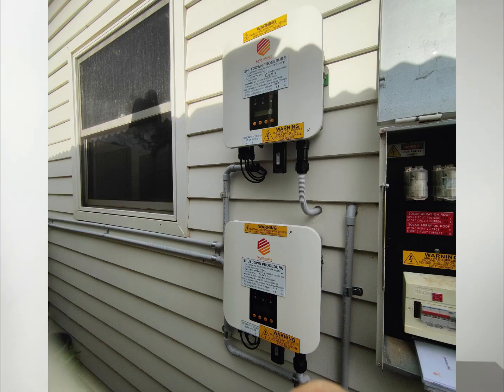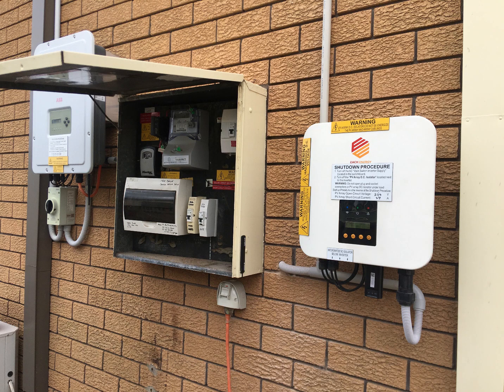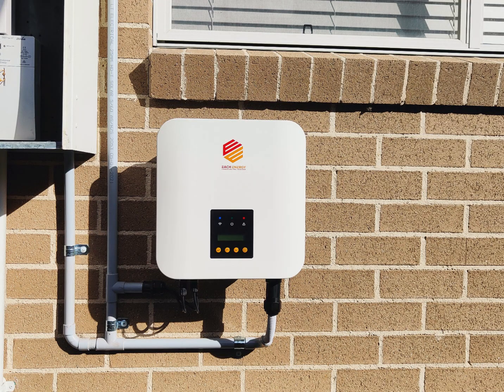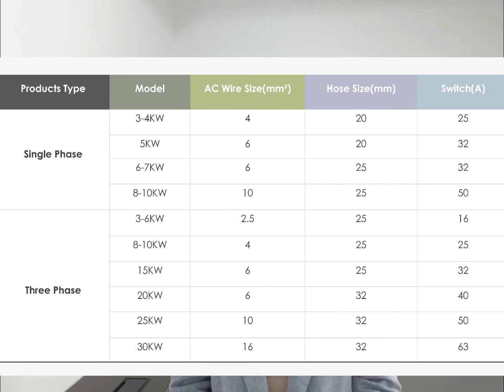Therefore, in terms of inverter selection, we prefer some brands with more powerful and stable performance, such as EACH Energy and SolarEdge. EACH Energy is more compact in both single-phase and three-phase models. It offers choice, matching the real condition during installation will exclude the possibility of any trip, which can greatly reduce your customers' complaint cost to you. In summary, the high grid voltage caused by the popularization of solar energy is indeed a problem that cannot be ignored. That's all.